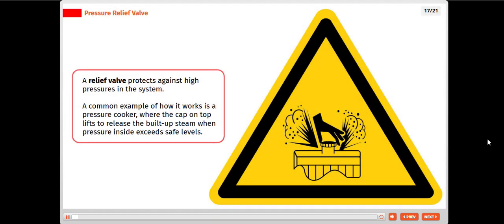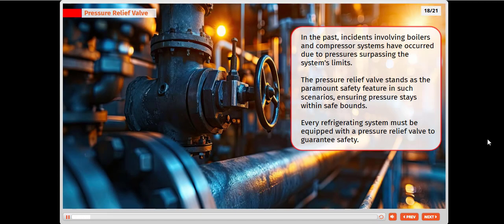A relief valve protects against high pressures in the system. A common example of how it works is a pressure cooker, where the cap on top lifts to release the built-up steam when pressure inside exceeds safe levels. In the past, incidents involving boilers and compressor systems have occurred due to pressure surpassing the system's limits. The pressure relief valve stands as the paramount safety feature in such scenarios, ensuring pressure stays within safe bounds. Every refrigerating system must be equipped with a pressure relief valve to guarantee safety.